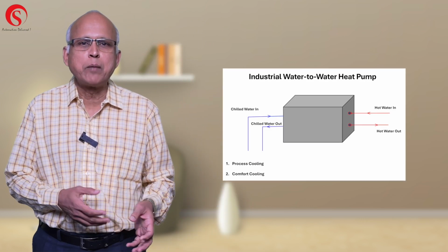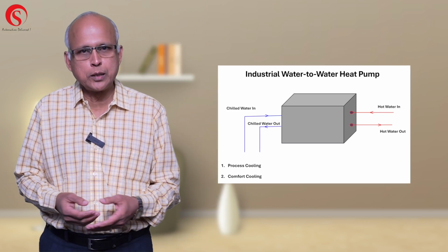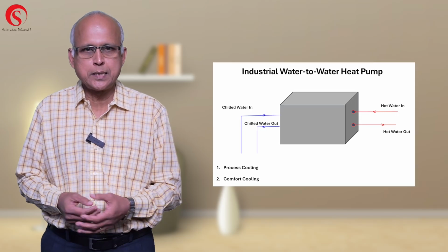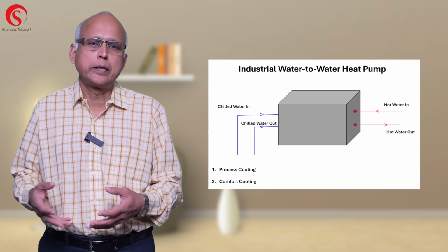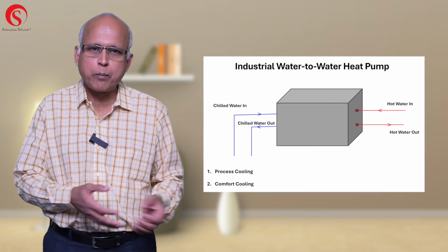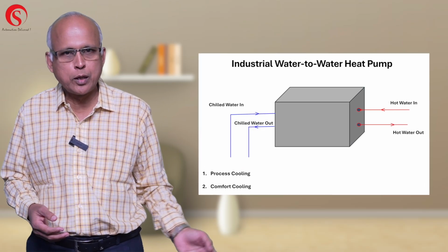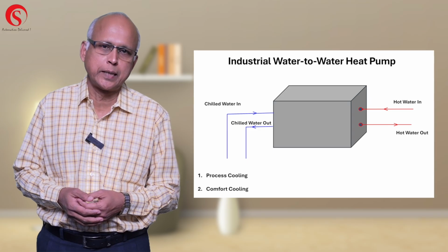In the last episode, we discussed how we could use the cold air coming out of the heat pump to improve the value being provided by the heat pump. So one of the questions I continuously encounter when I visit industries for heat pumps is, can it simultaneously generate chilled water for us? The answer is yes. If we take a water to water heat pump, automatically we can generate chilled water on one side and hot water on the other side.